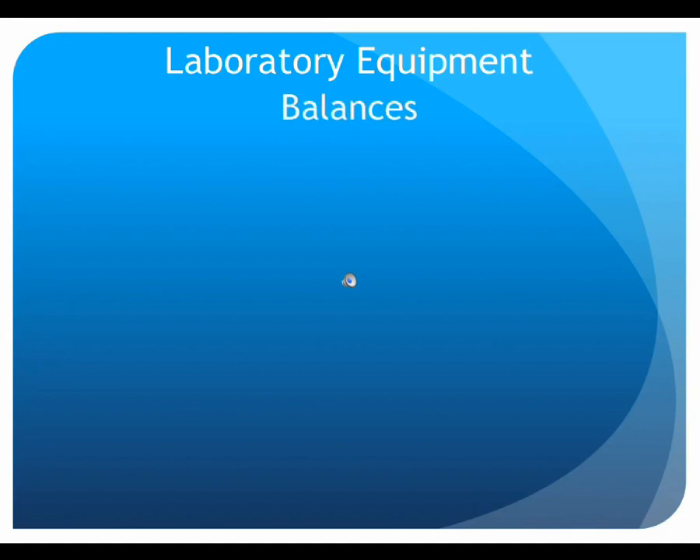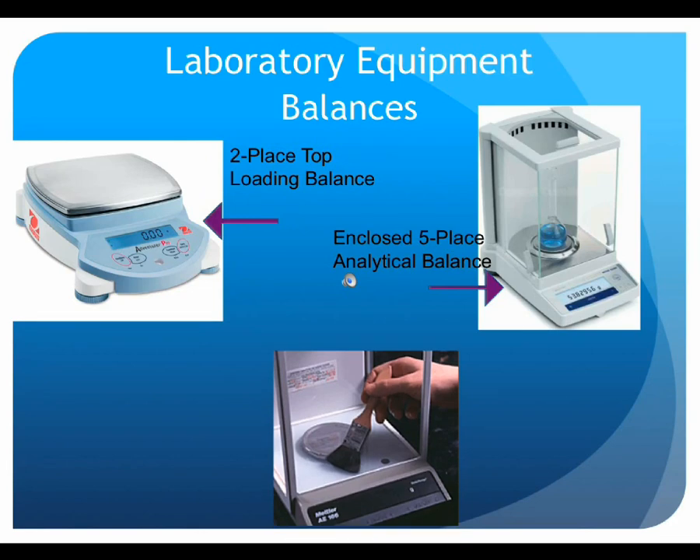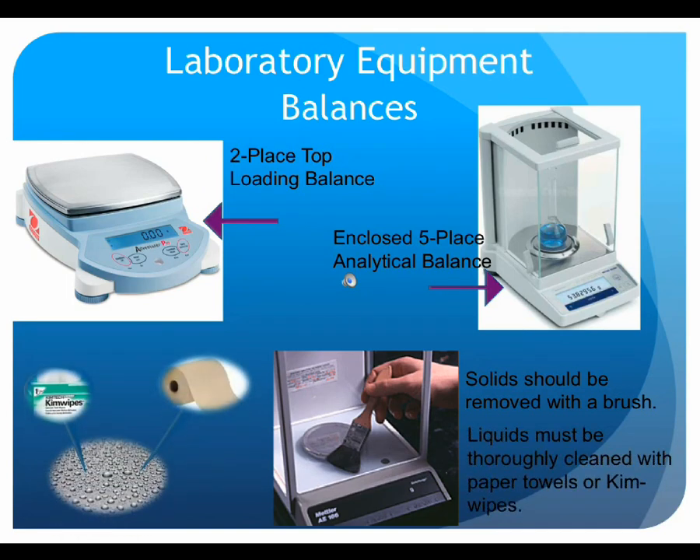The integrity of electrical cords for all types of electrical equipment is important. Balances are typically positioned in a designated area and not routinely moved. There are two primary classes of balances: two-place top-loading balances and four-to-five-place enclosed analytical balances. With either type, the pan and electronics must be free from contamination of solid and liquid materials. If even small amounts of chemicals are spilled onto the balance, they must be thoroughly cleaned up immediately. Solid material can be swept up using an appropriate brush, and liquid should be cleaned using Kimwipes or damp paper towels. Ensure that the balances are clean before use and are left clean when lab is complete.